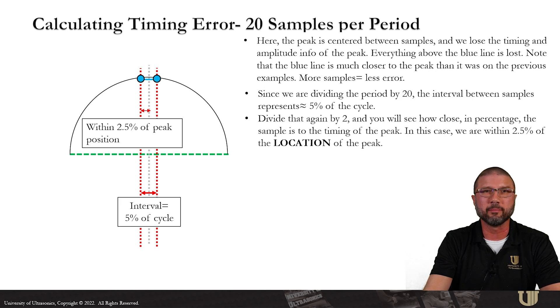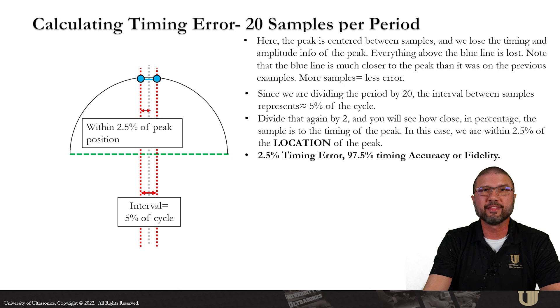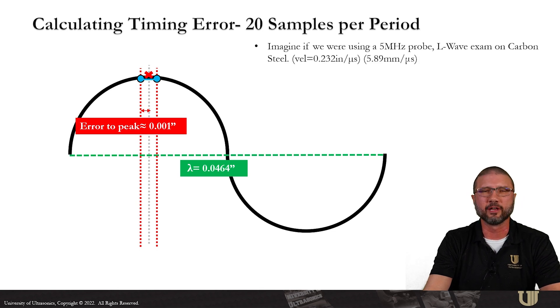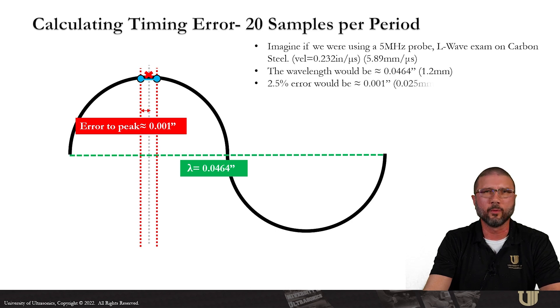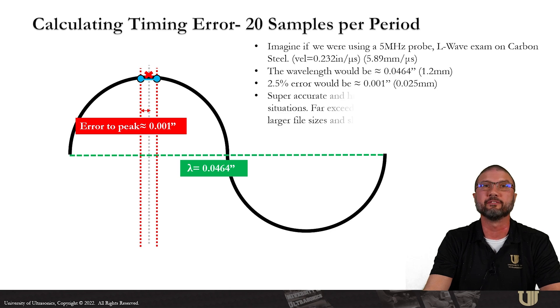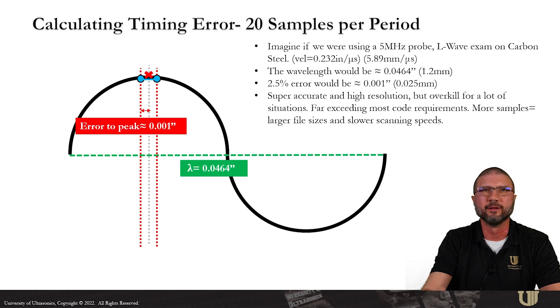Since we're dividing the period by 20, the interval between samples represents about 5% of the cycle. Divide that again by two and we're within 2.5% of the location of the peak — 2.5% error, 97.5% timing fidelity. For a 5 megahertz L-wave exam on carbon steel, that 2.5% error equates to about one thousandth of an inch — super accurate, really high resolution, but it might be overkill for some situations and far exceeds most code requirements. More samples also means larger file sizes and slower scanning speeds.